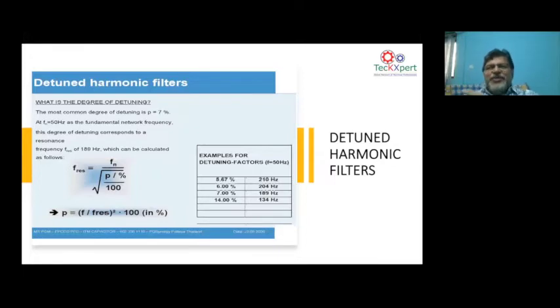That means again, you are not amplifying a third harmonic current or a fifth harmonic current when you put a 14%. So that means in the majority of office buildings and banks and data centers, where you have a lot of third harmonic, it is always safer to install a 14% detuned reactor so that you're detuning the circuit far away from the third harmonic frequency. Go to the next.